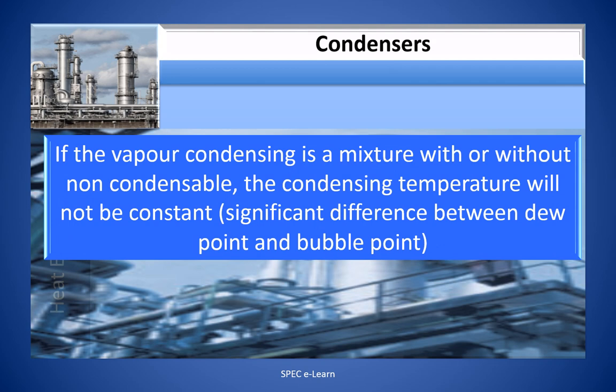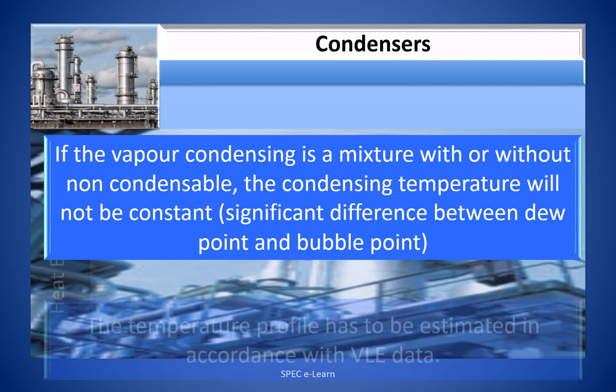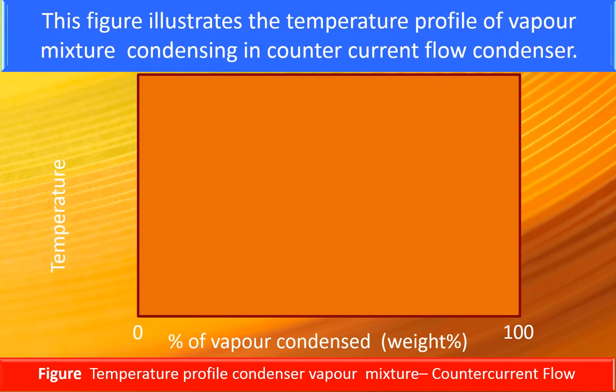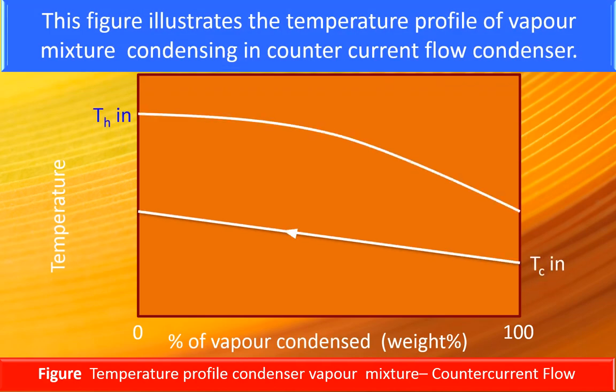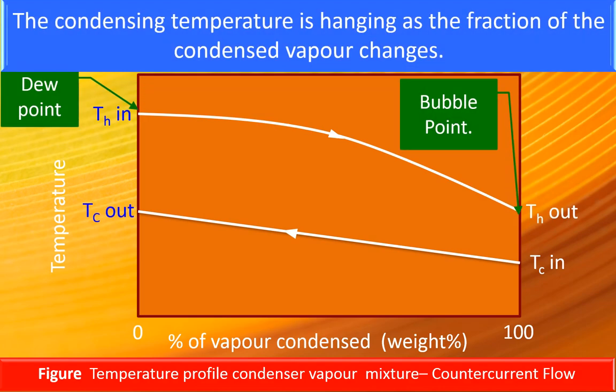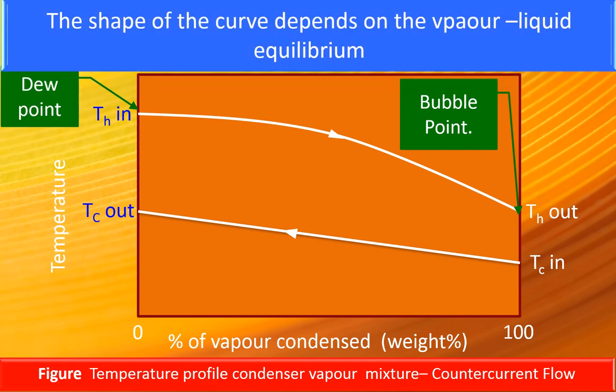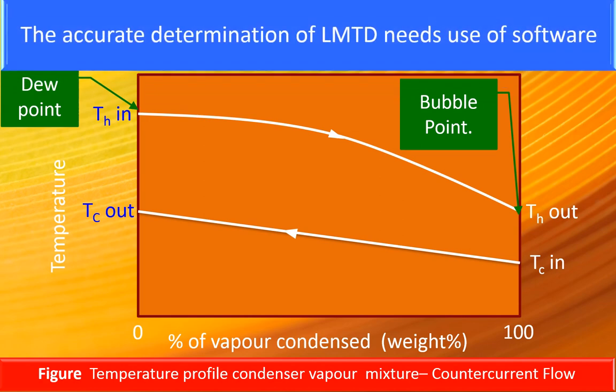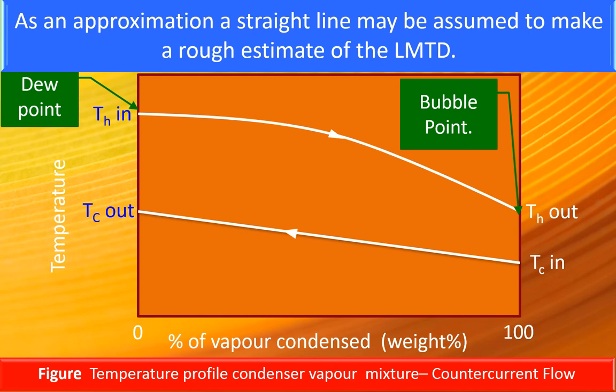If the vapor condensing is a mixture with or without non-condensables, the condensing temperature will not be constant. The temperature profile must be estimated in accordance with VLE data. The condensing temperature changes as the fraction of condensed vapor changes, and the shape of the curve depends on the vapor-liquid equilibrium. Accurate determination of LMTD requires software; as an approximation, a straight line may be assumed to make a rough estimate of the LMTD.